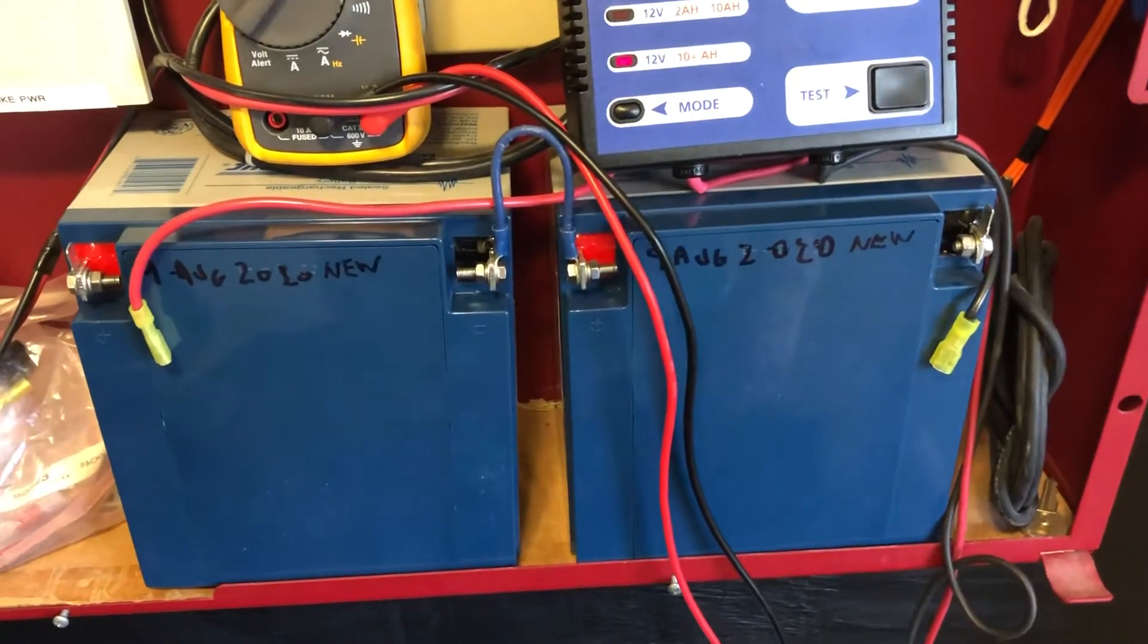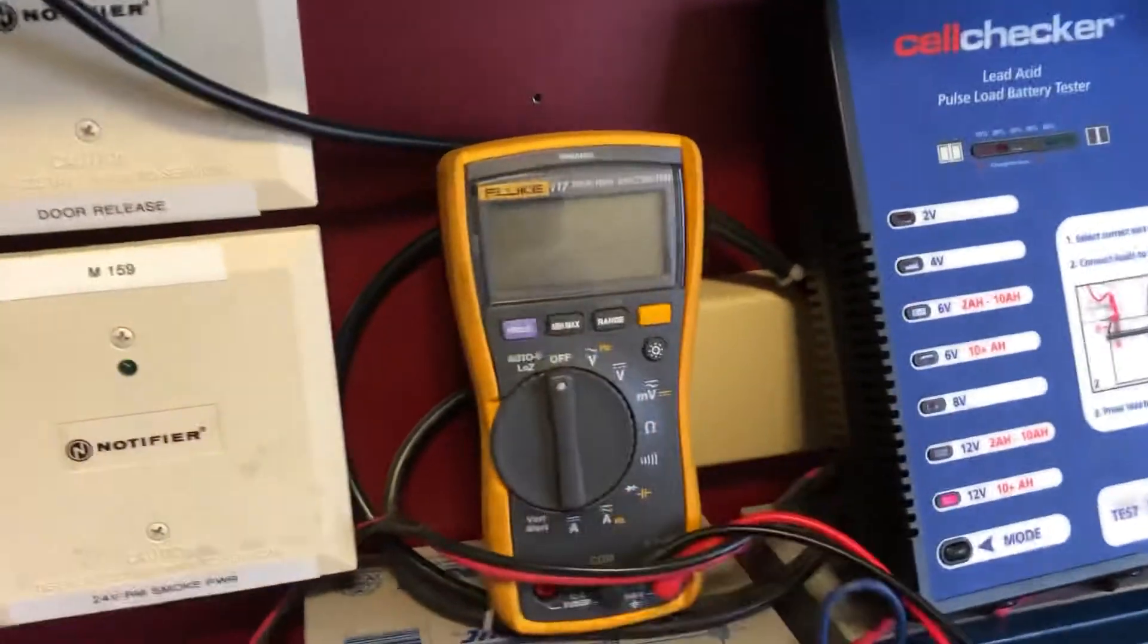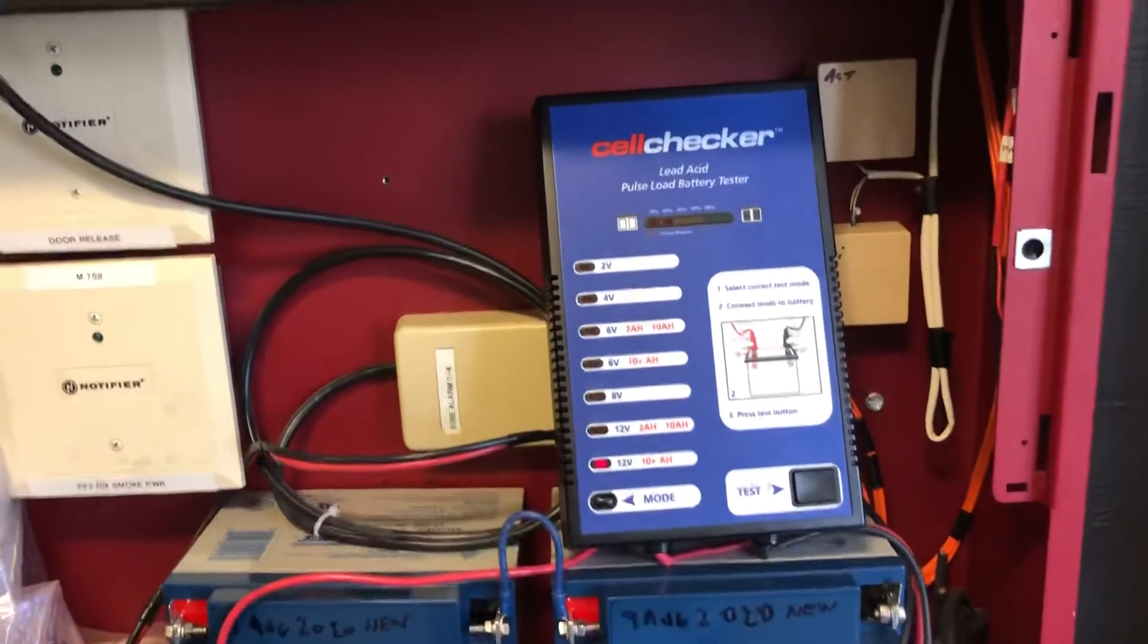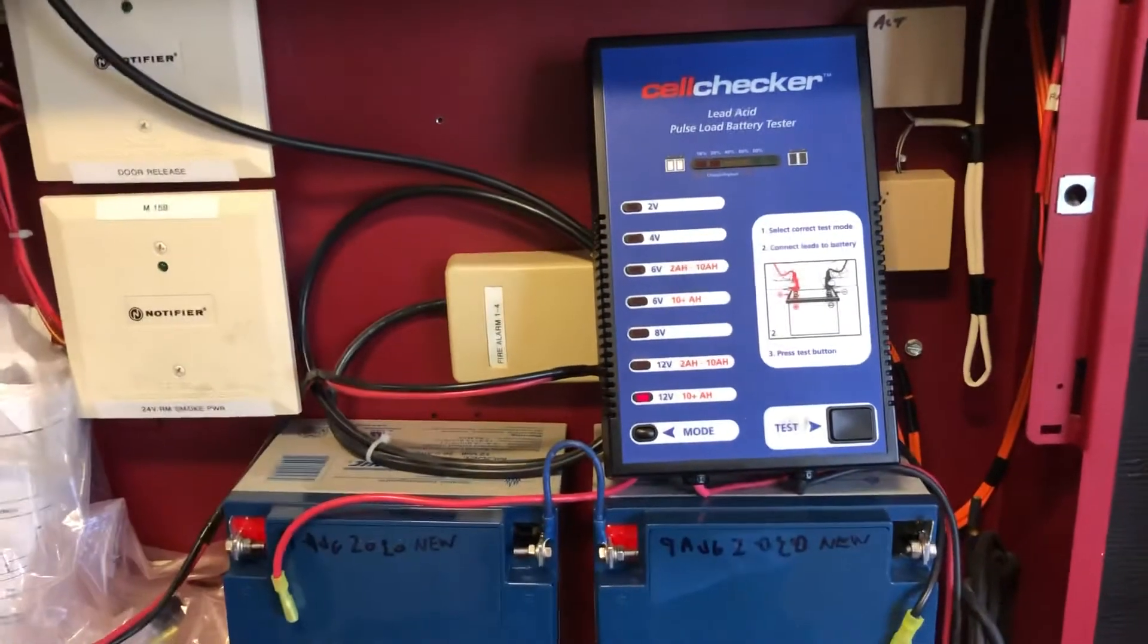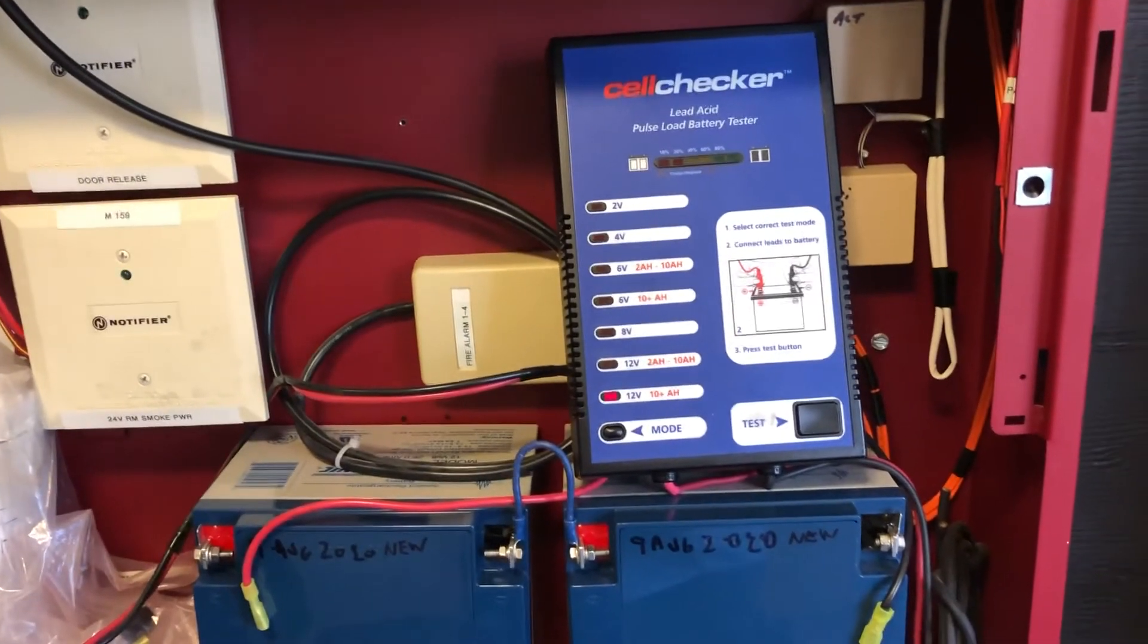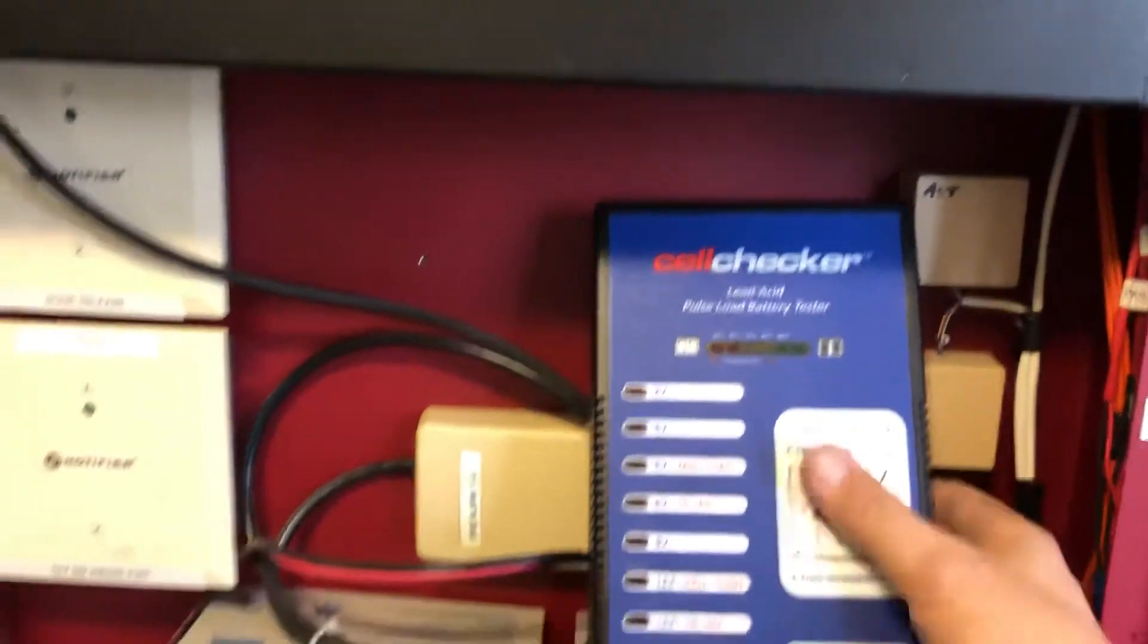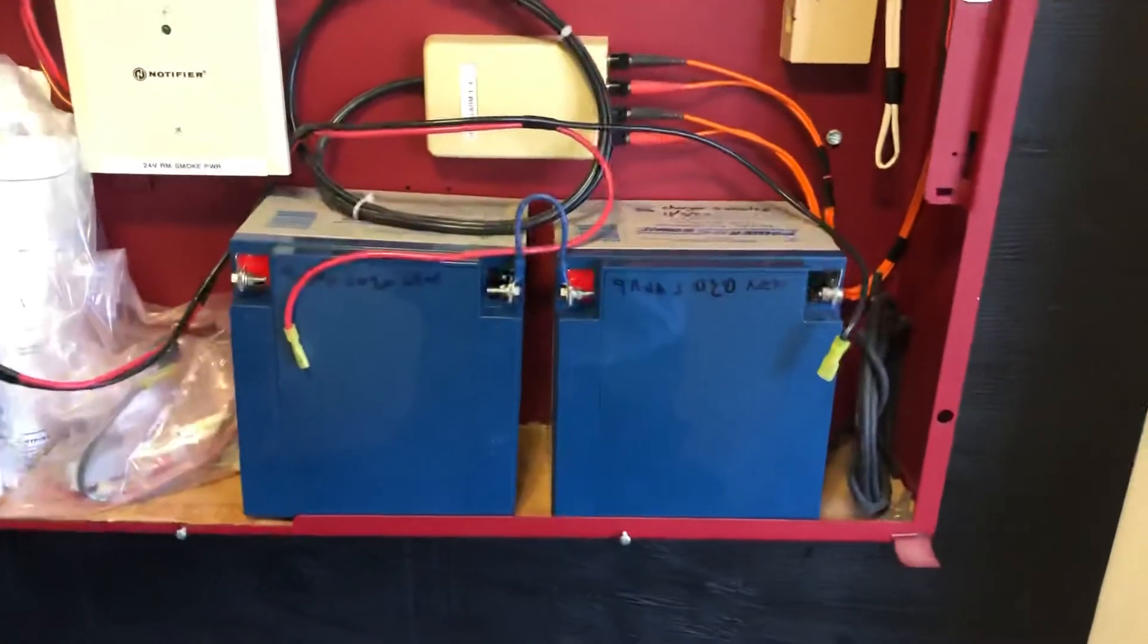Always also check the code. A lot of people are still going off that five year time frame for replacing batteries. I believe NFPA 72 changed at some point to whatever the manufacturer's recommendations were. Five years is still generally a long time for a battery. Three to five years is about how long they last.